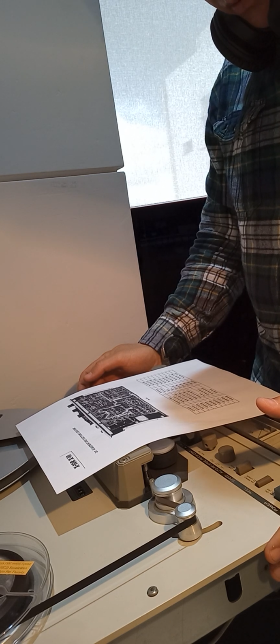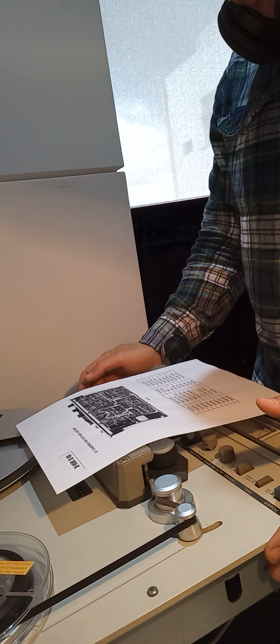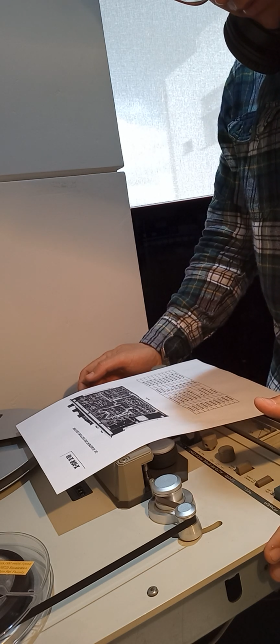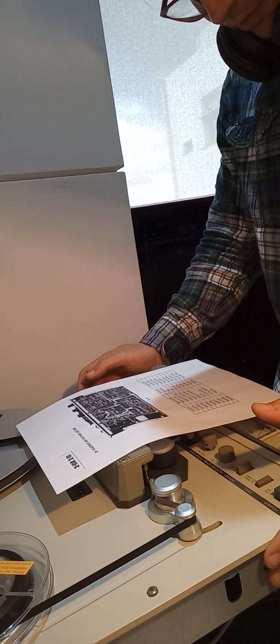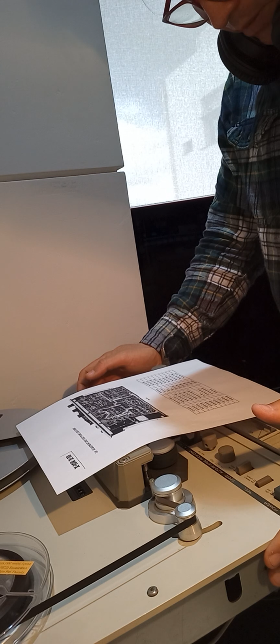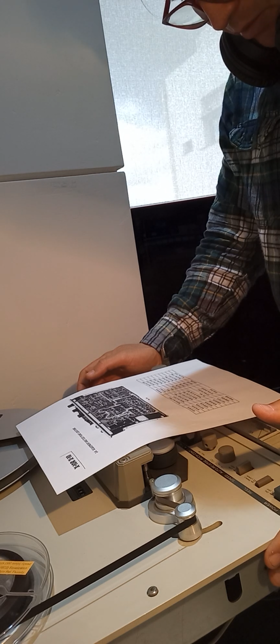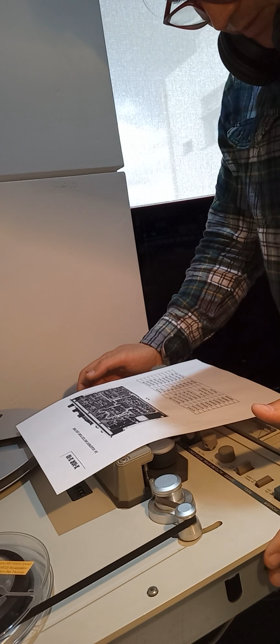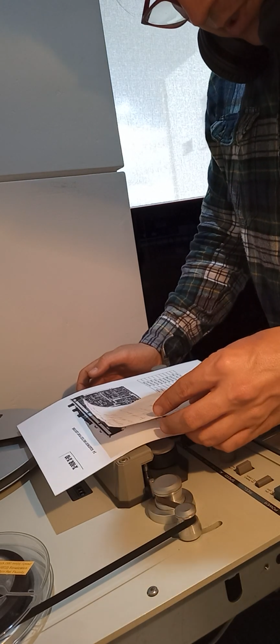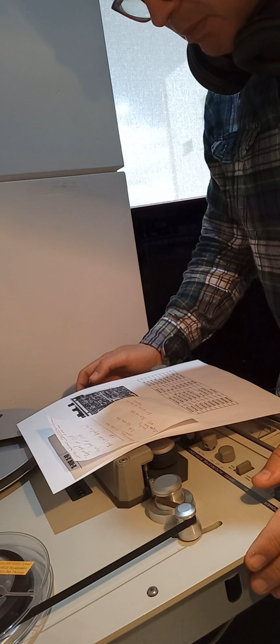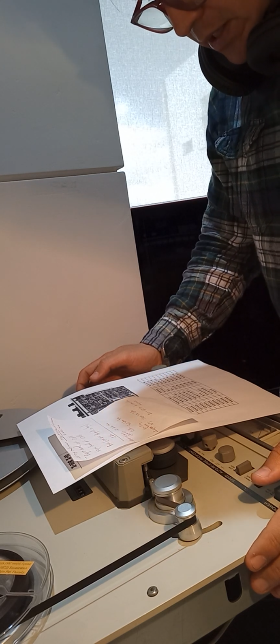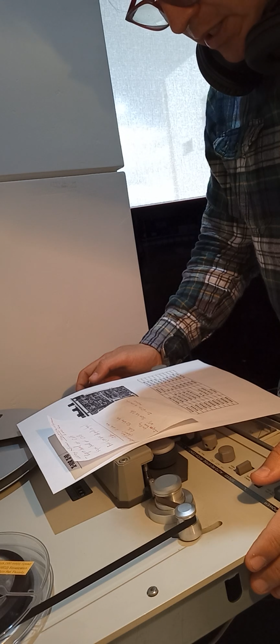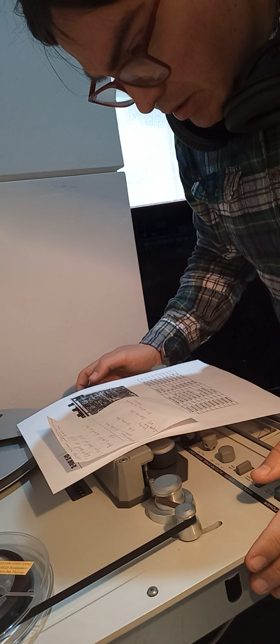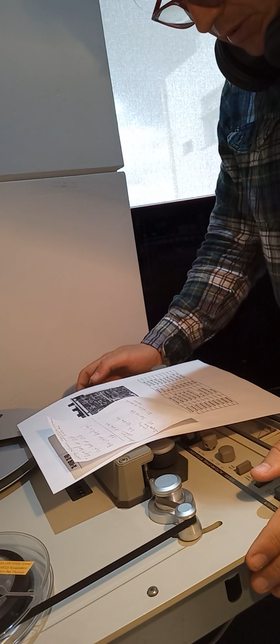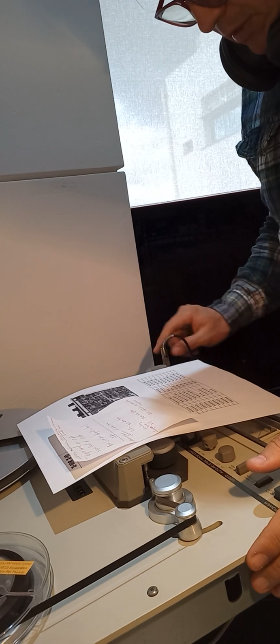playback EQ, high forward, high reverse, low forward, low reverse, excuse me. dBx level. I'm guessing that's the internal compressor. I think that should be part of the EQ. VU meter, monitor playback. Output level. There's one. I'm looking for bias trap. It says bias trap. Record EQ, record bias. So record gain and it's bias. Bias over bias. Depends on tape. It depends on the tape. So I gotta look all that stuff up.